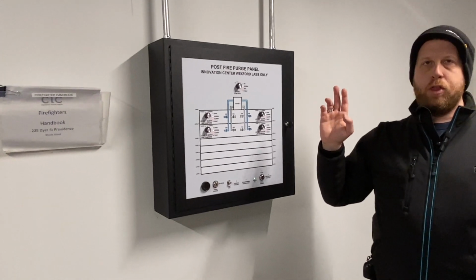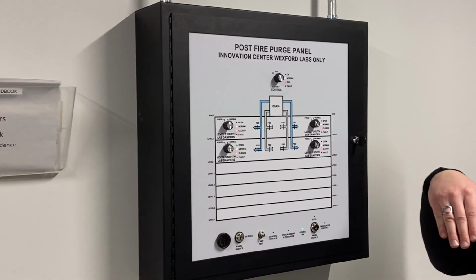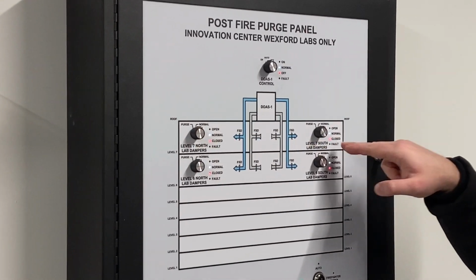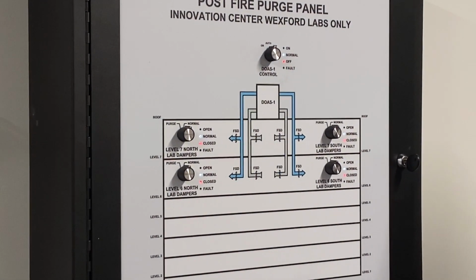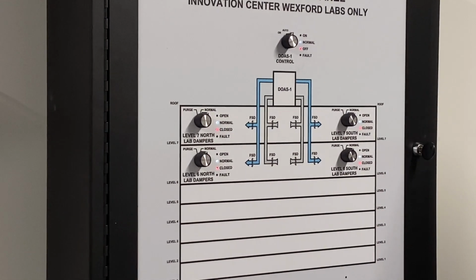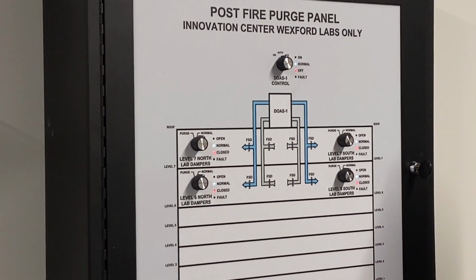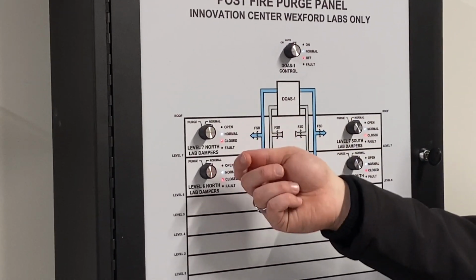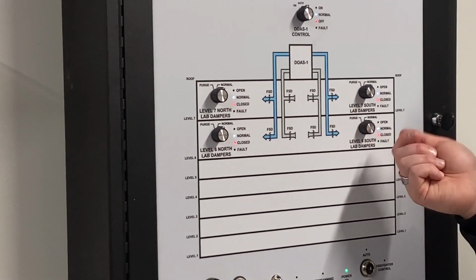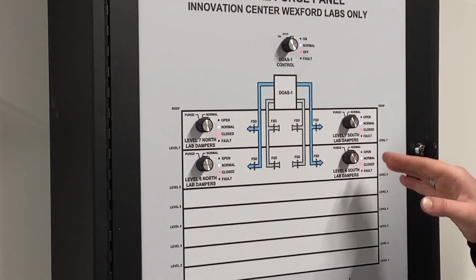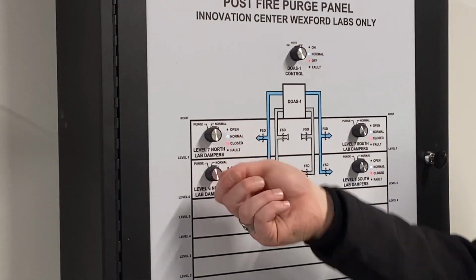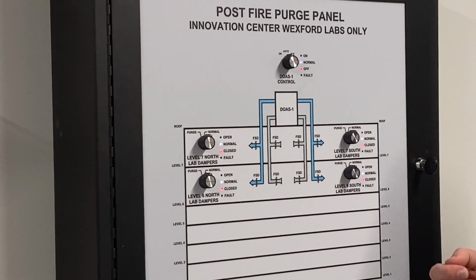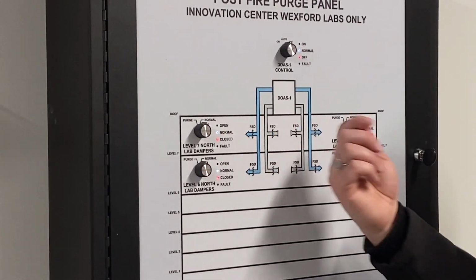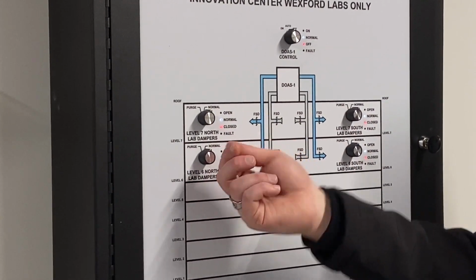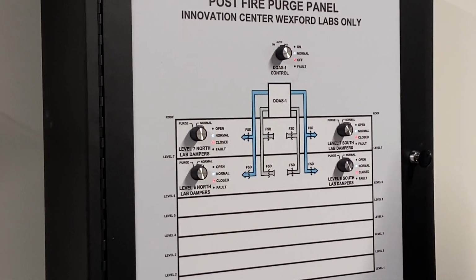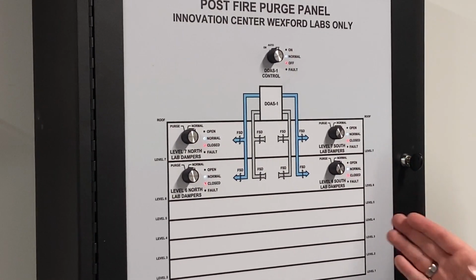Like I said, those dampers that I showed you on the 7th floor, there's 2 dampers for us. It's either going to be the north or the south set of dampers. And there's 2 sets per zone, so it's got a supply and return. So they come in firefighter control, they turn on DOAS 1, and then they can put everything into normal. Once they're in purge control, all the dampers will close, and then they can individually do 4 zones. They can turn all the other ones normal or close because you're in purge mode, and then purge, and it'll just open those set of dampers. You set them all closed, and you're probably going to trip a static pressure safety.